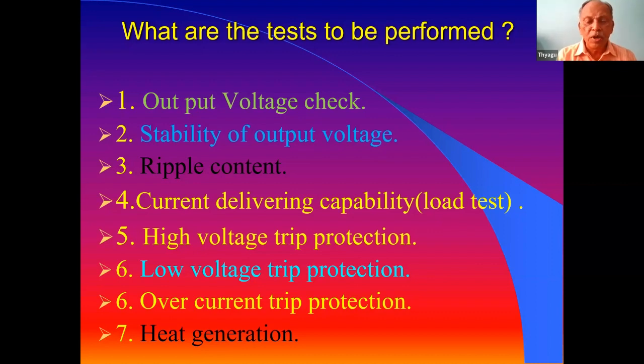The other one is the low voltage trip. When the voltage goes down, it will try to draw more current, so there should be a low voltage trip as well. Over current trip is also very important - suppose we have a 13.8 volt power supply rated for 25 amps; if the current drawn is very high, there should be a trip protection. That is the over current trip.